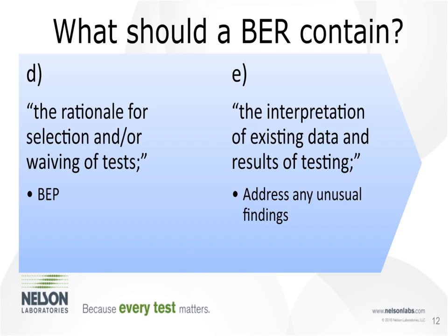So it's important when you're reviewing your data that comes back from the laboratories that somebody is reviewing that who has the knowledge and the experience, knowing not just what's required in the test, but also what the standards require. This is also a great area to address any unusual findings if you failed a test, or maybe you have a known cytotoxic material, which is a common finding in medical devices. You can address the risk in this section of your BER.